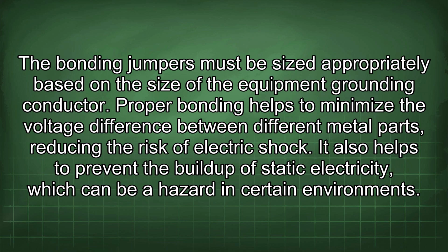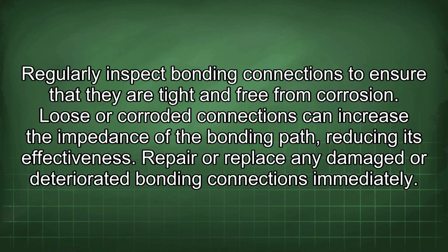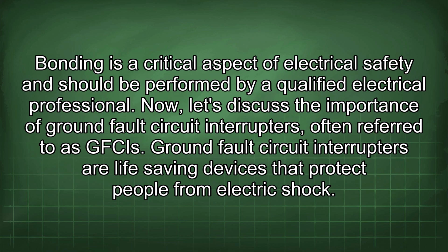Proper bonding helps to minimize the voltage difference between different metal parts, reducing the risk of electric shock. It also helps to prevent the buildup of static electricity, which can be a hazard in certain environments. Regularly inspect bonding connections to ensure that they are tight and free from corrosion. Loose or corroded connections can increase the impedance of the bonding path, reducing its effectiveness. Repair or replace any damaged or deteriorated bonding connections immediately. Bonding is a critical aspect of electrical safety and should be performed by a qualified electrical professional.